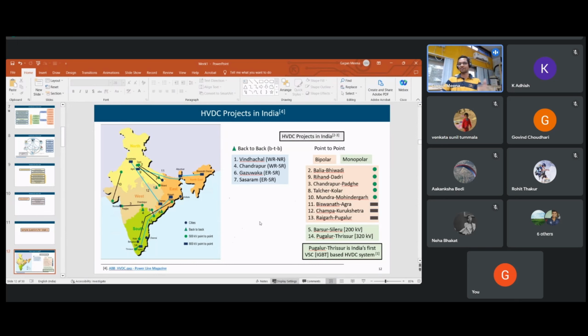Also, one more important point: from line number 1 to line number 13, all these lines were based on thyristor, so they were all current controlled, based on silicon thyristor SCR technology. But recently we have also come up with India's first VSC, voltage source converter based HVDC system, which is the 14th, between Pugalur and Thrissur. It is very recent and was commissioned last year itself.